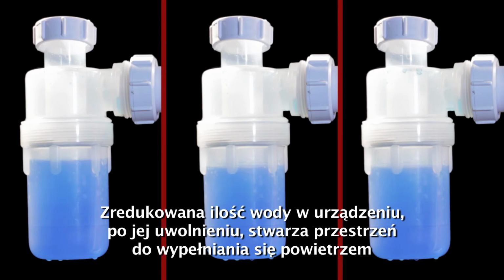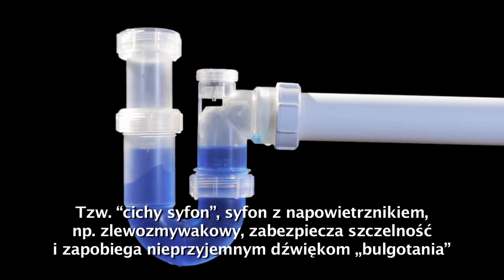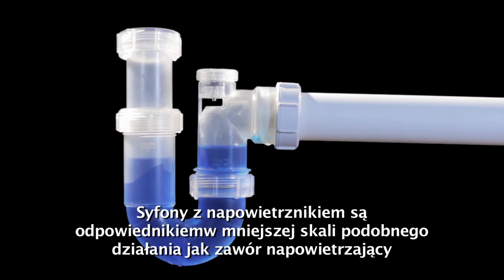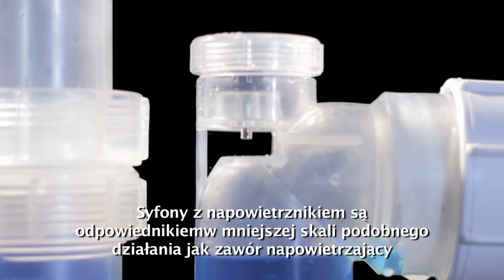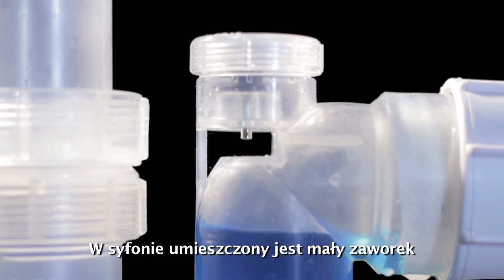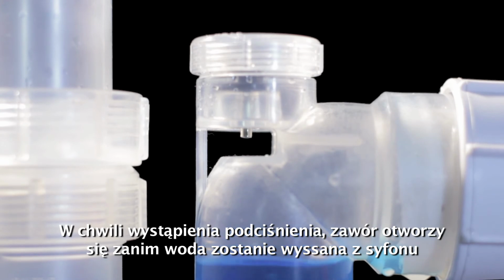A silent trap fitted to an appliance, such as a sink basin, will protect seal integrity and remove unpleasant glugging sounds. Silent traps incorporate the small-scale use of an AAV principle utilizing a small valve within the trap. Under negative pressure, the valve opens prior to the water seal being displaced.